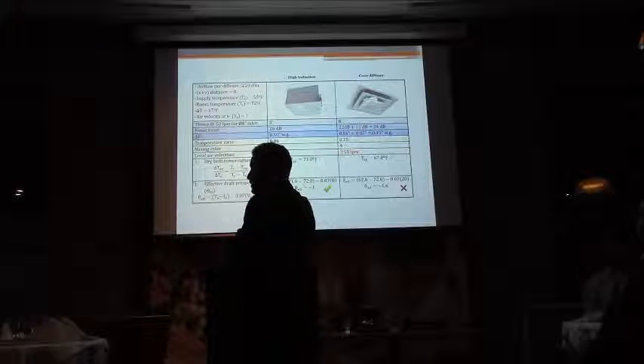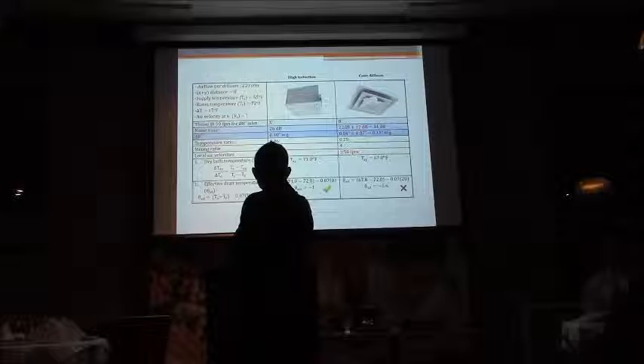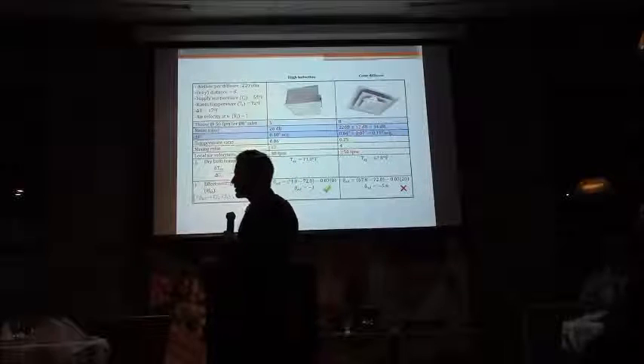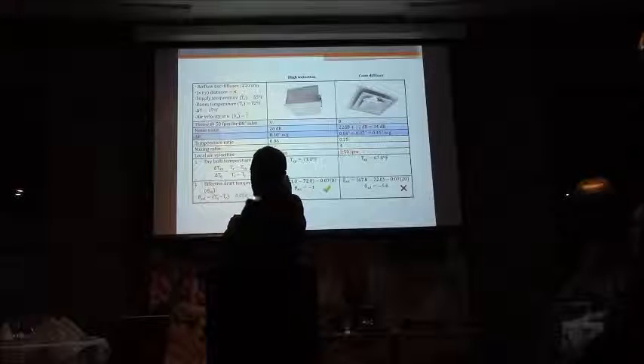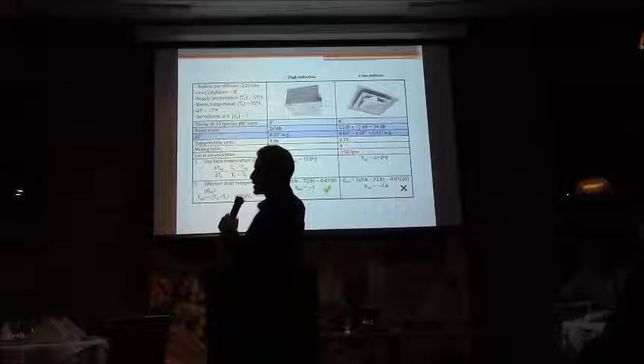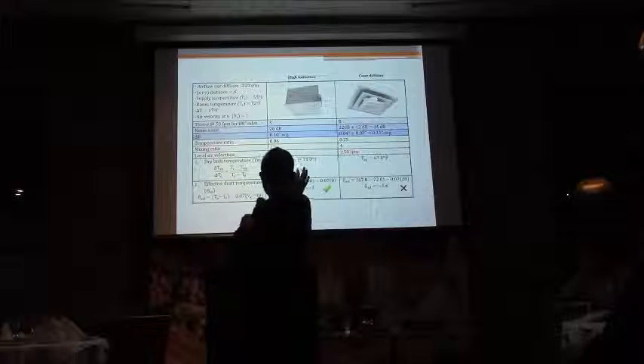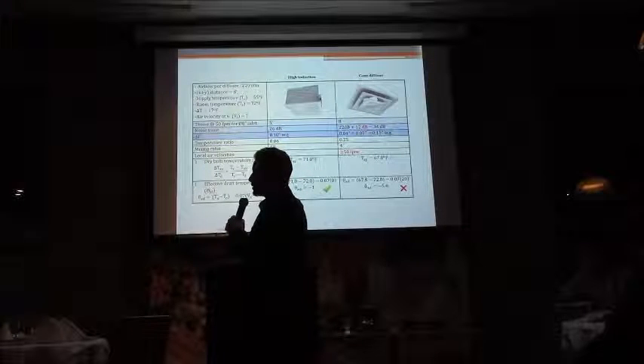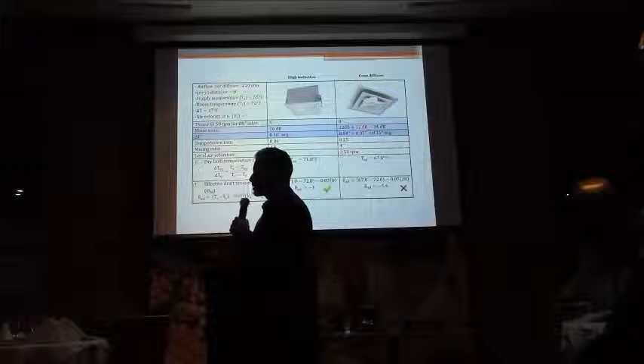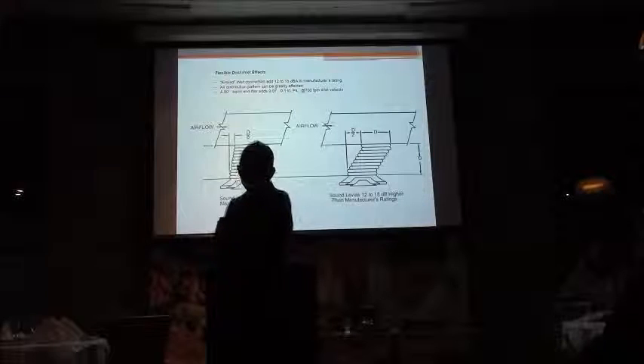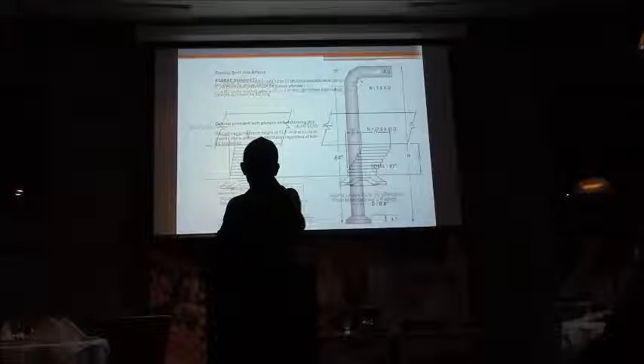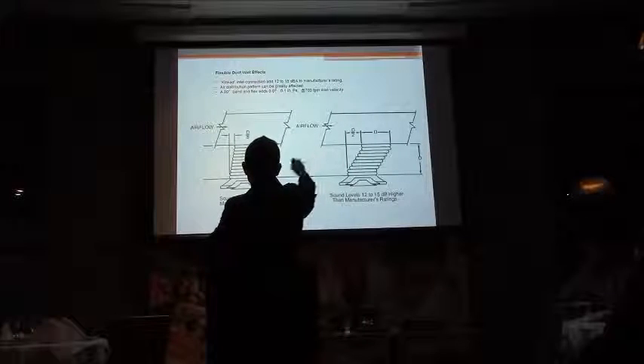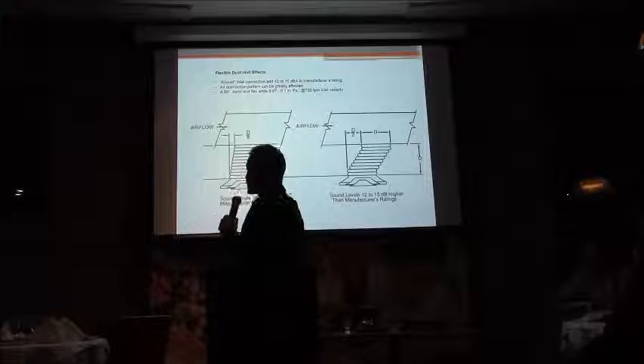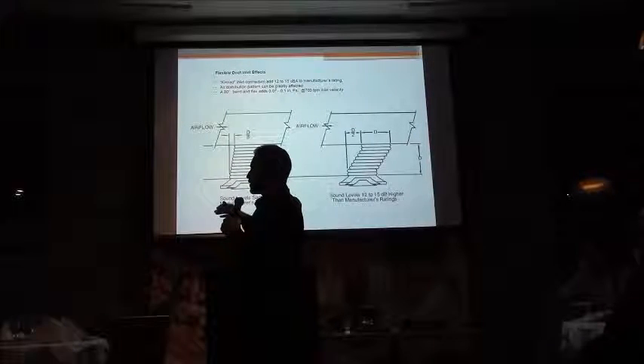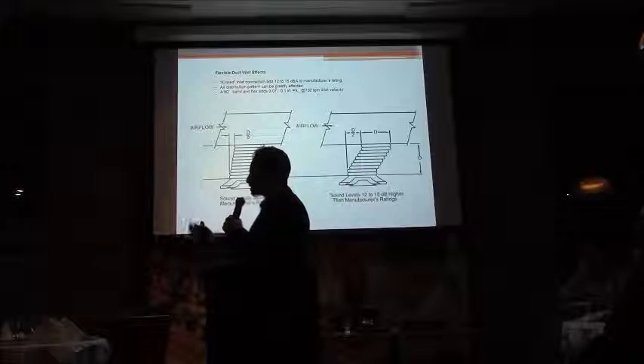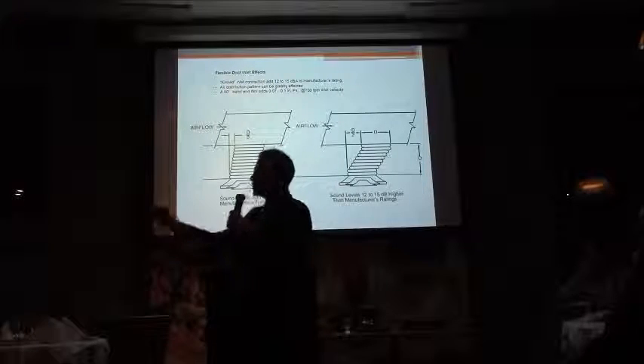That's pretty severe. But 34 dB is still pretty low in terms of hearable sound, right? You can go up to 34, and it's even more. I added 12, but it's 12 to 15 decibels in reality, so it's 34 to 37 decibels. I took this from ASHRAE. This is how ASHRAE mentions it: if you have a thin connection, you have up to 12 to 15 decibels, because they consider a worst case scenario installation where the contractor probably looped a few times around the diffuser.